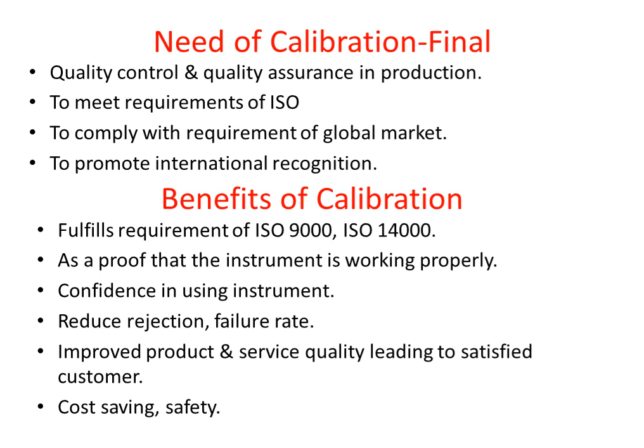So what are the benefits of calibration? It fulfills the requirements of ISO 9000 and ISO 14000. As a proof that the instrument is working properly, we need the calibration. Confidence in using the instrument. This is the basic benefit of calibration. Reduce rejection and failure rate. To improve the product and service quality leading to the satisfied customer. For cost saving and safety, calibration is needed. So by calibrating, you are saving the expenditure and you are ensuring more safety.